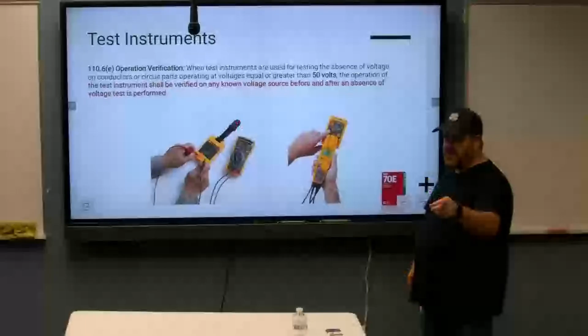Before we test a circuit, we need to make sure that we test it before we even touch it. What's the best way to do that? Use an induction tester. Now, somebody said earlier they don't like them because they can give you inaccurate readings. Somebody said that, right? Yep. They're right. It can give you a false reading, but here's how it works. If it's working correctly, it's going to give you a false positive, not a false negative.